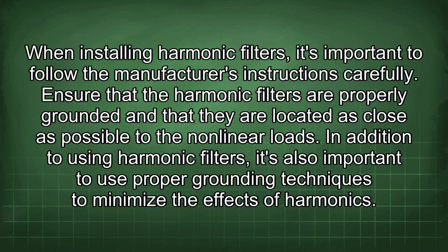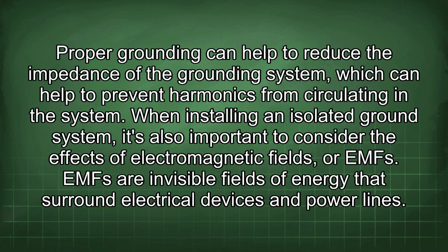Ensure that the harmonic filters are properly grounded and that they are located as close as possible to the nonlinear loads. In addition to using harmonic filters, it's also important to use proper grounding techniques to minimize the effects of harmonics. Proper grounding can help to reduce the impedance of the grounding system, which can help to prevent harmonics from circulating in the system.